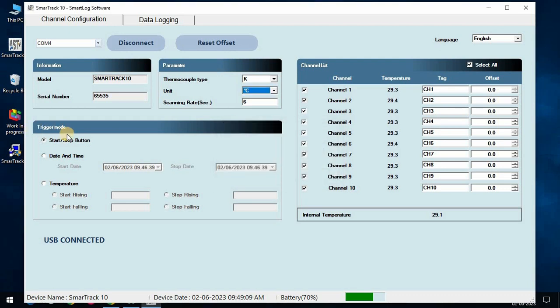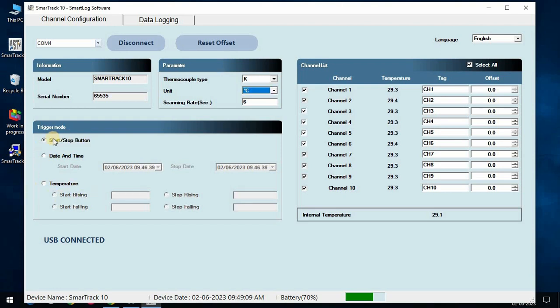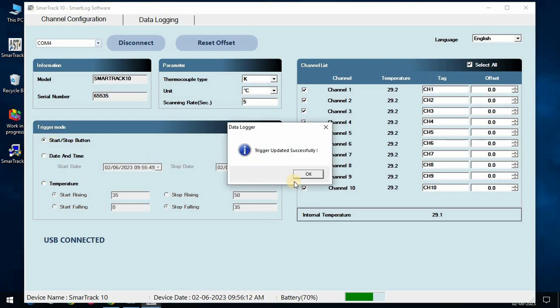In trigger mode, we have three different types of trigger mode. First start and stop button. Second time and date. Third is temperature. For the complete thermal profiling curve, we suggest to choose start and stop button as the trigger mode.